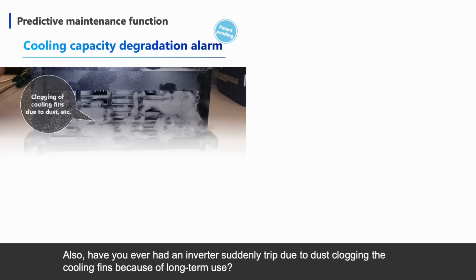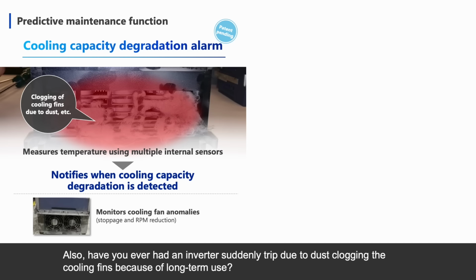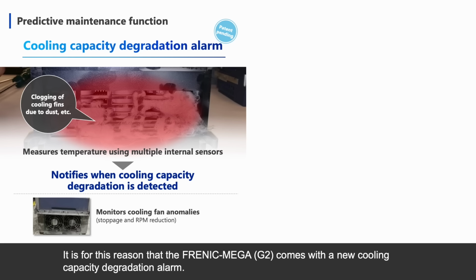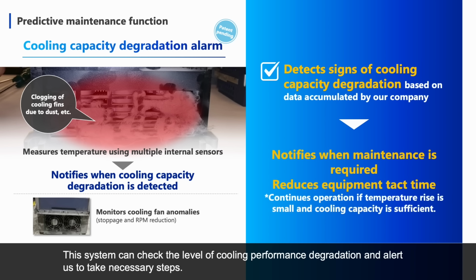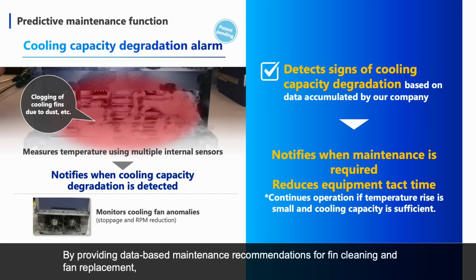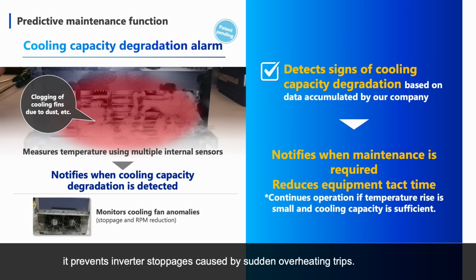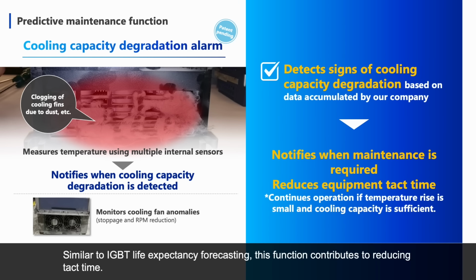Also, have you ever had an inverter suddenly trip due to dust clogging the cooling fins because of long-term use? It is for this reason that the FRENIC-MEGA G2 comes with a new cooling capacity degradation alarm. This system can check the level of cooling performance degradation and alert us to take necessary steps. By providing data-based maintenance recommendations for fin cleaning and fan replacement, it prevents inverter stoppages caused by sudden overheating trips. Similar to IGBT life expectancy forecasting, this function contributes to reducing takt time.